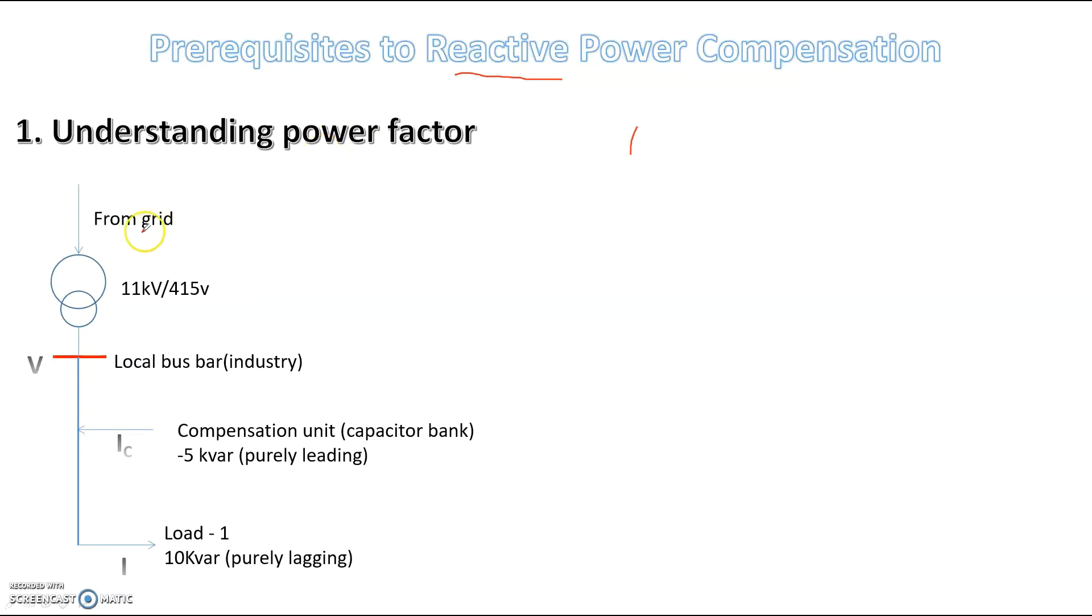The first thing that you need to understand is the single line diagram. This is the supply grid. This is a step down transformer, stepping down a 11 kV voltage level to a 415 volt line to line voltage. We will be having a local bus bar. From this particular place, your jurisdiction will start. You have to take care of whatever is happening here. Whatever is going on here is not under your control. It is totally governed by the power utility, the grid or the state electricity board.